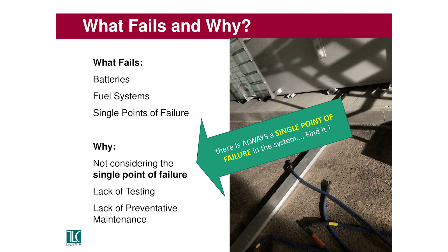So let's start by talking about what typically fails and why. Lots of stuff can fail. I'm going to talk about single points of failure, but the majority of the time it has something to do with the batteries or the fuel, not the actual engine generator itself usually. It's because the batteries weren't charged or it wasn't able to start, or the same thing with the fuel system. That's usually because there was a lack of testing, lack of preventative maintenance.